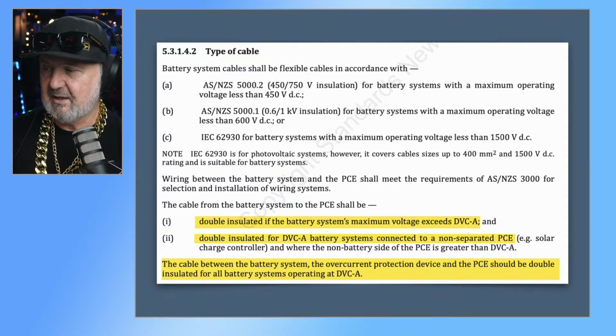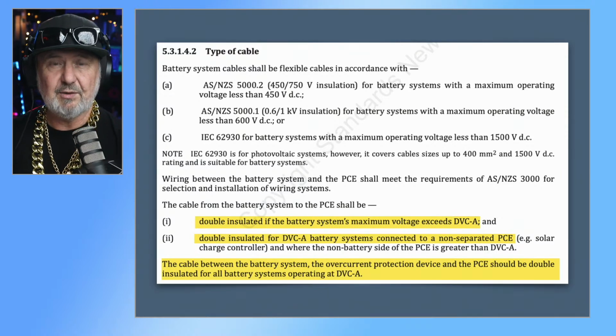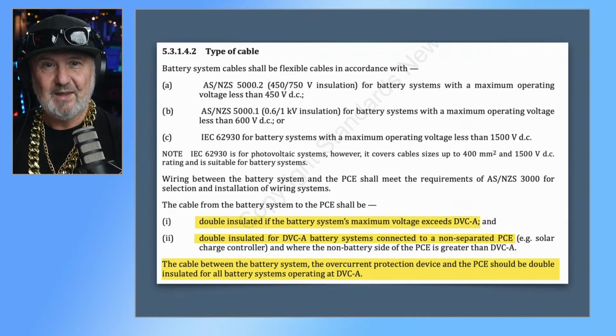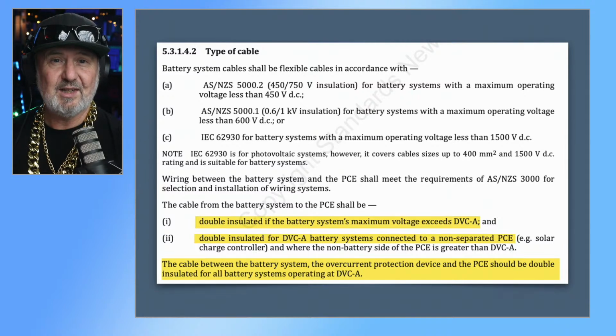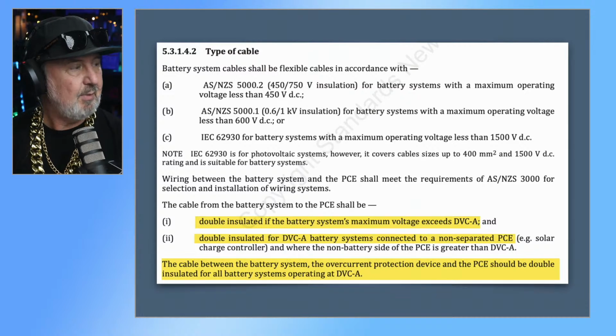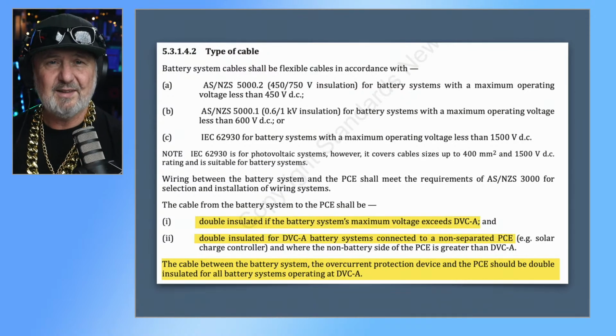Coming back to the slide here, DVC-A is less than 60 volts DC. In fact, the wording is must not exceed 60 volts for more than 0.2 of a second under any operating conditions. So it's very, very limited to 60 volts, DVC-A. And so most nominal 48 volt lithium ion batteries will be within that DVC-A range. It's when you're looking at some other esoteric battery types or even good old flooded lead acid. Flooded lead acid often would go over 60 volts for a 48 volt bank in equalization. So they become DVC-B. So DVC-B is between 60 and 120 volts DC, and DVC-C is above 120.